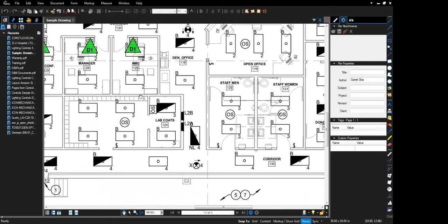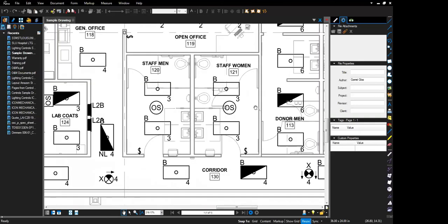So a good example of an ultrasonic application would be a restroom that has partitions or stalls in it. These style restrooms where you have different stalls would be an application where you'd want to use ultrasonic only. The reason I say ultrasonic only is because with a dual technology one, typically the way those are set from the factory is if the light turns off, then both technologies have to see you to turn it back on. Once it's on, if either one sees you, it maintains the lights on. But once it turns off, they both have to see you.